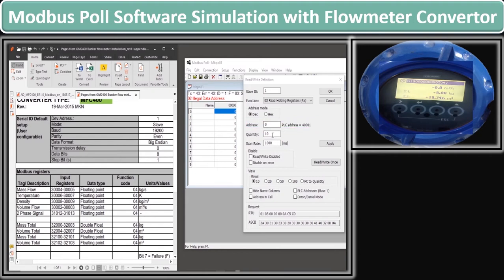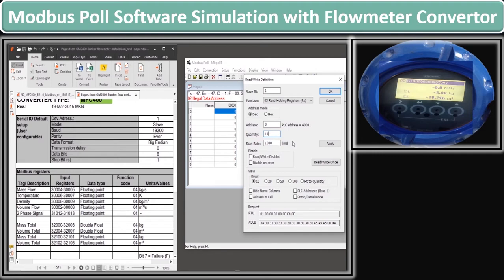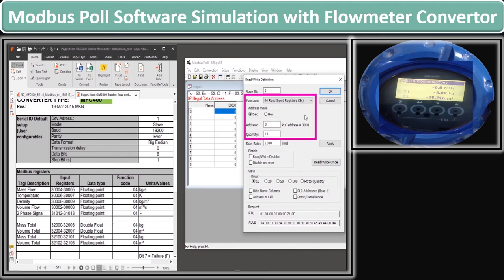In the quantity section, the value indicates how many registers we want to see starting from our address register 30000. We put the number 14 here so that it covers values up to register 30014. Then we change the function code, which is given as 04 in the parameter list. You can see that after changing the function code, our PLC address range comes into the range of 30000.